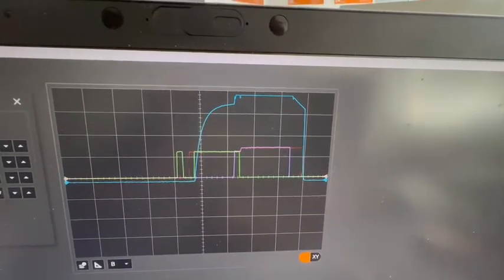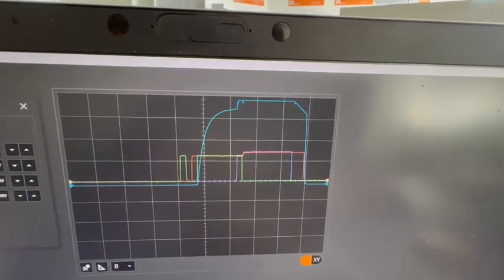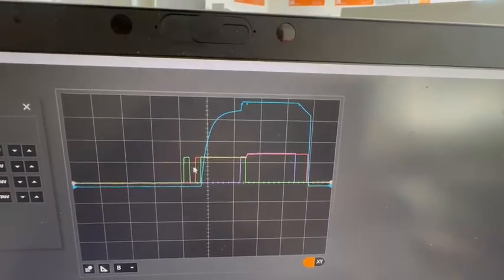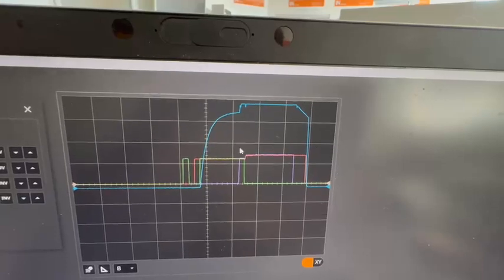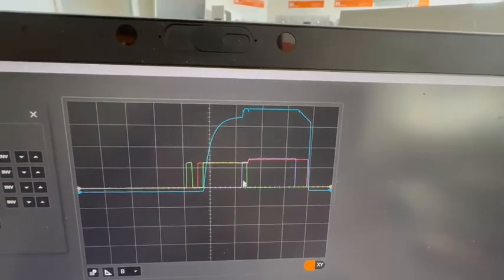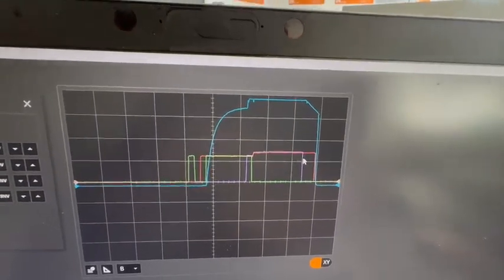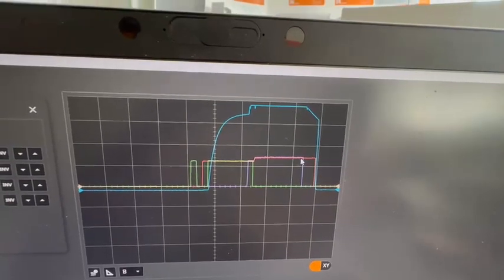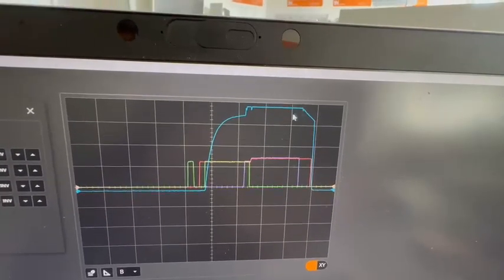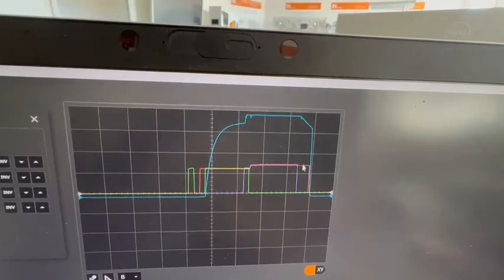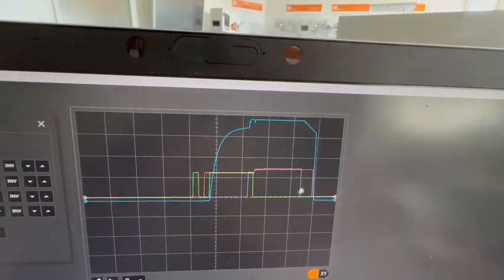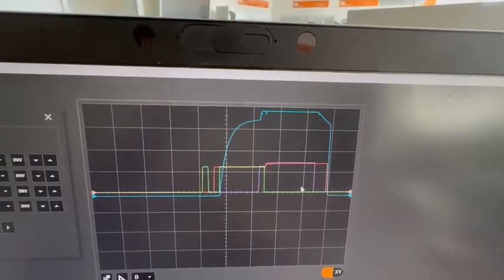Okay, that's that one there. So the negative relay is on all the time until the end here. So the positive one is only on right here. If we switch that off now and we don't see any change in the voltage until we get to this point, then we know the positive relay has been welded shut.